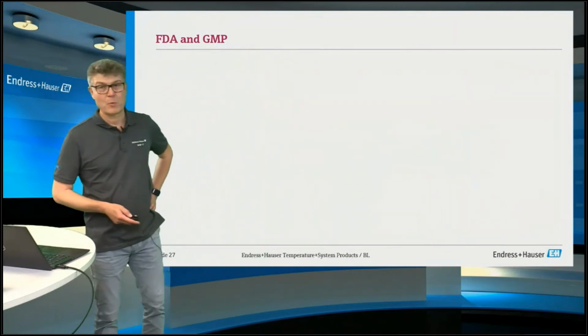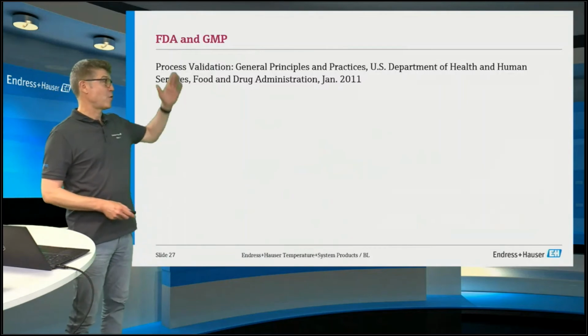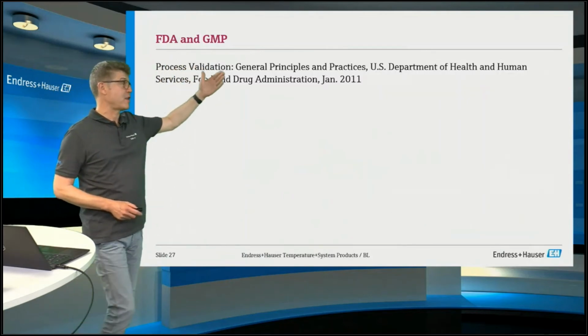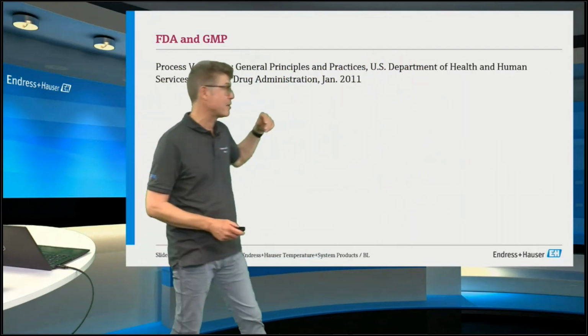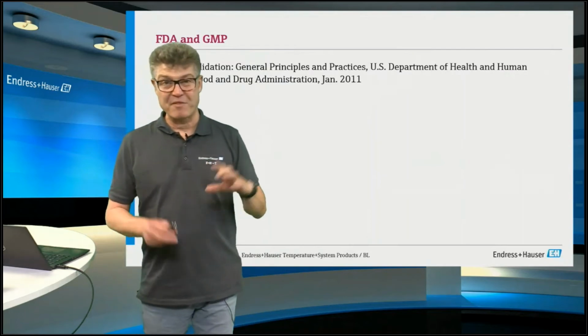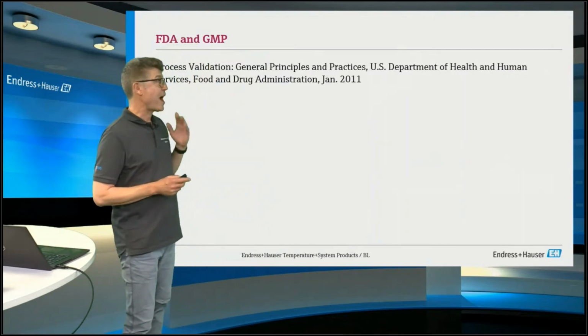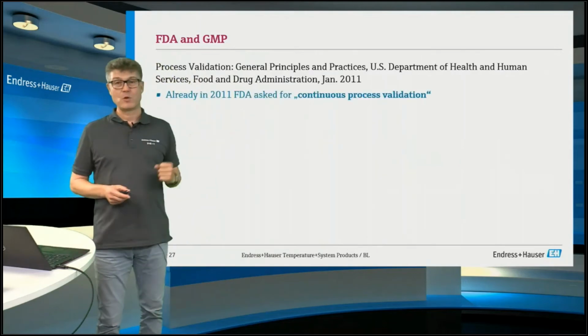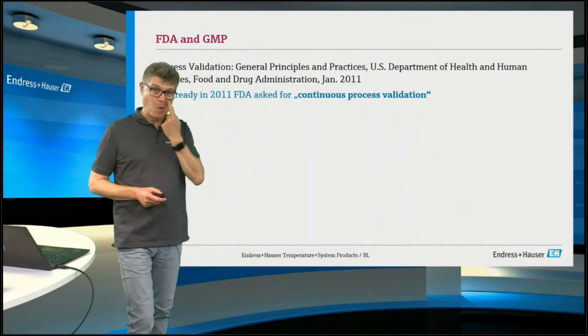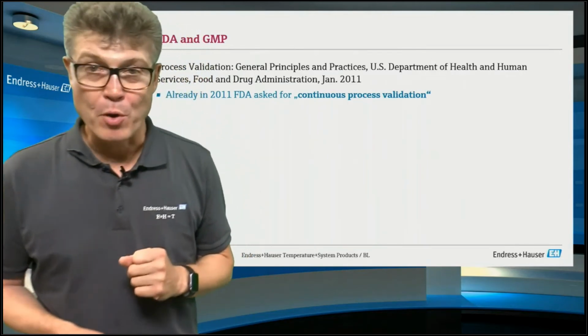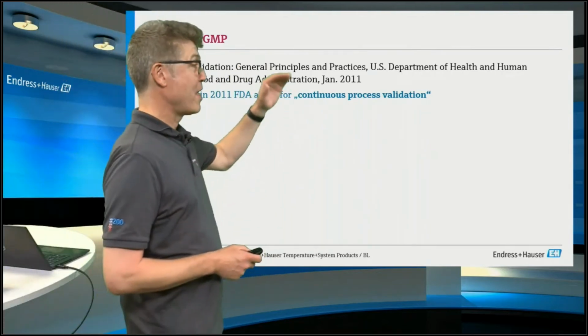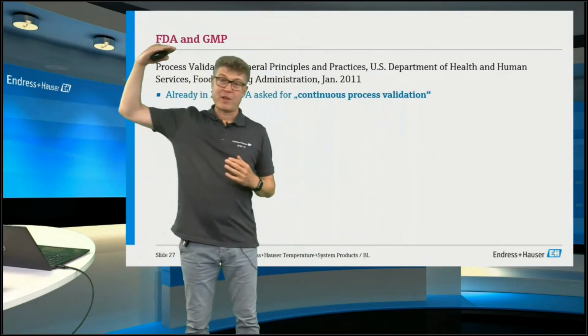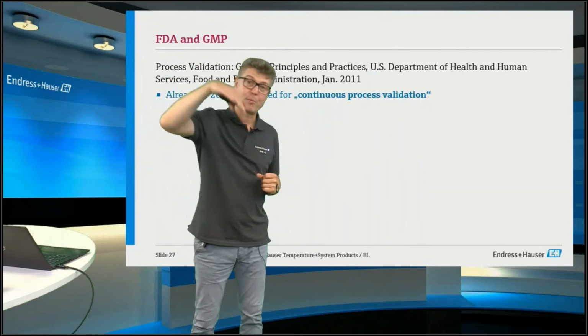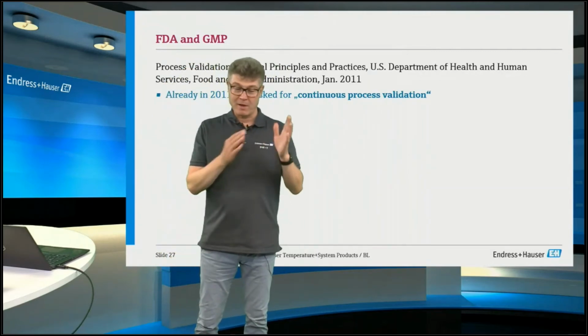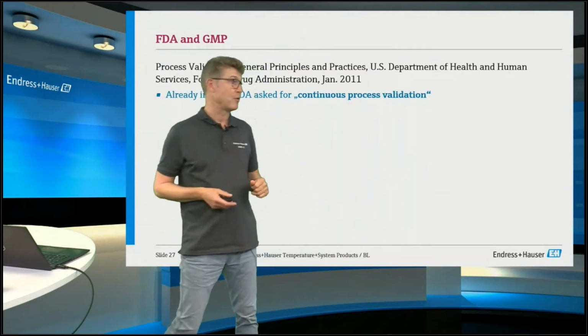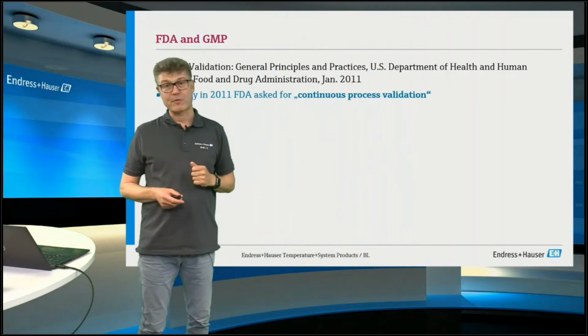So what is written there? What is really the wording? The FDA rules of process validation, general principles and practices, a US document published in 2011, more than 10 years ago, ask for continuous process validation. What we are doing is continuous process calibration. We perform this calibration every time the sterilizer cools down, the milk processor goes down, every time, continuously. It cannot be switched off. It's always on, continuous process validation. We do this now; they asked for it 10 years ago.